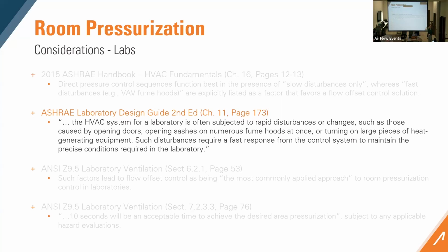Regional Jason added, pharma applications get audited and FDA/EU don't allow time out proof. Yeah, so are you specifically talking about clean room applications or compounding pharmacies? We have clean rooms, yeah. In clean room applications, we would typically see a vestibule or an ante-room. And we would have pressure monitors at those spaces that would be tied back to a BMS to be able to trend that pressure at all times to make sure that pressurization is always maintained.